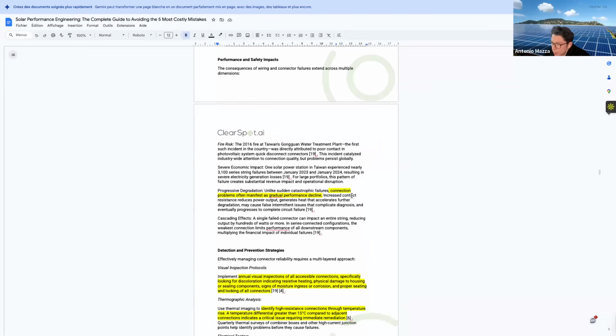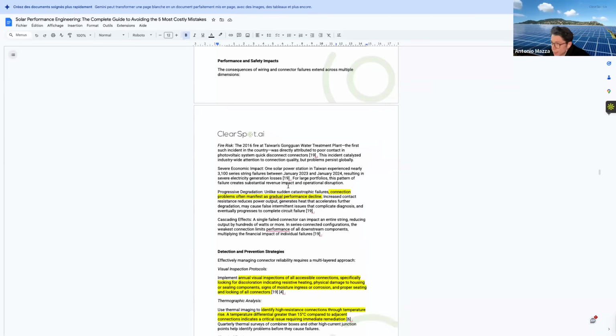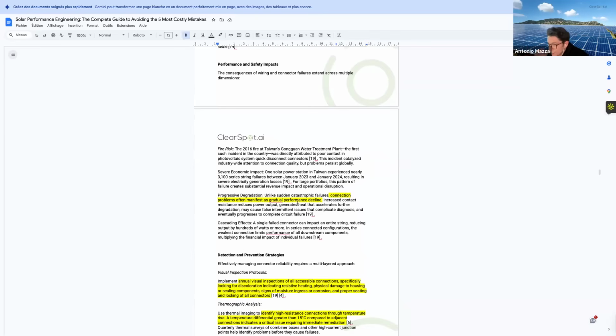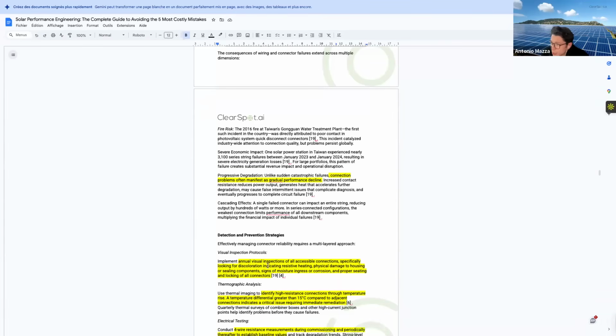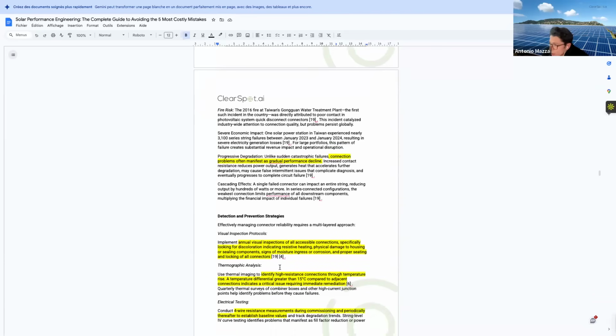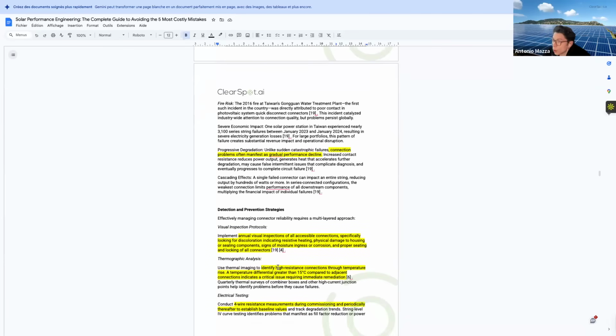We know the importance of connectors and need to pay attention. In terms of degradation, the degradation of all assets is progressive, so you want to monitor it and avoid it before you have any cascading effects. So, prevention strategy: visual inspection protocols, an annual visual inspection of all accessible connections, specifically looking for discoloration indicating resistive heating, physical damage to housing or sealing components, and signs of moisture ingress or corrosion. Proper sealing and locking of all connectors.